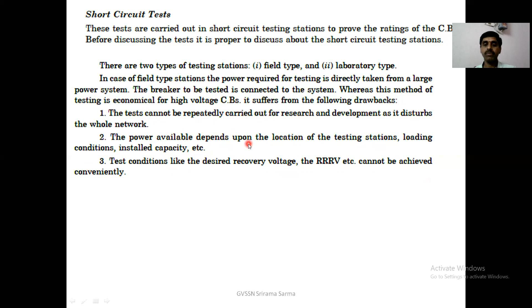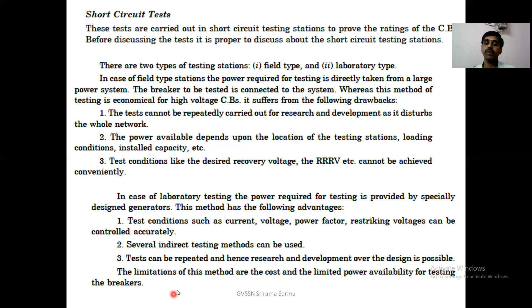In the laboratory type of testing, the power required for testing is provided by specially designed laboratory generators. This method has the following advantages. Test conditions such as current, voltage, power factor, and restriking voltage can be controlled accurately. Several indirect testing methods can be used. And tests can be repeated, hence research and development or design is possible. The limitations of this method are cost and limited power availability for testing breakers.